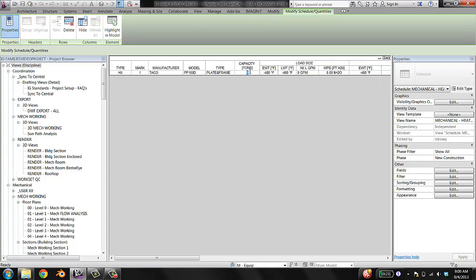Here's an interesting point. Whenever you see a unitless number, you want to be careful. In Revit, all of these values have units attached to them — Revit knows if it's a cooling load, a heating load, a temperature, or a pressure, and it assigns a unit. So even though this heading says 'Capacity Tons,' that's just text; I could change it to whatever I want. Just because the heading says one thing doesn't mean the unit is actually what I want it to be. I'll check this in Formatting.